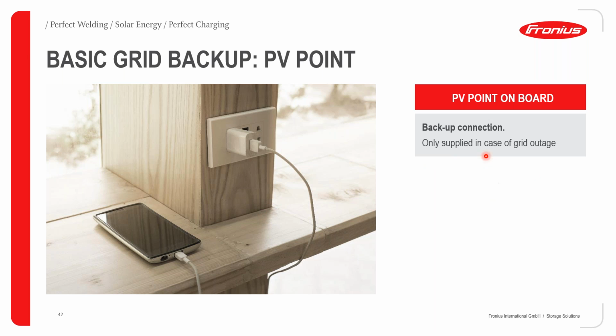Ordinarily, the PV point would not be supplied with power. So if you have some loads connected to the PV point, it is advisable that you also incorporate an automatic transfer switch, or a transfer switch of some kind, to make sure that there is a smooth transfer between grid and solar power depending on power availability. So once you have a grid outage and the PV point is powered up, when the grid returns there is a seamless transition, also by using this transfer switch I've talked about. And therefore, the grid continues to power your loads, and the PV point is disconnected by the inverter.